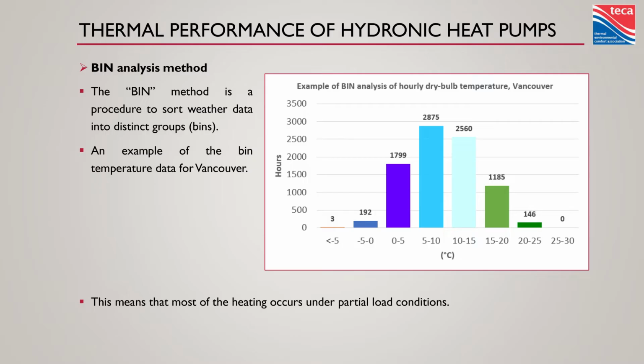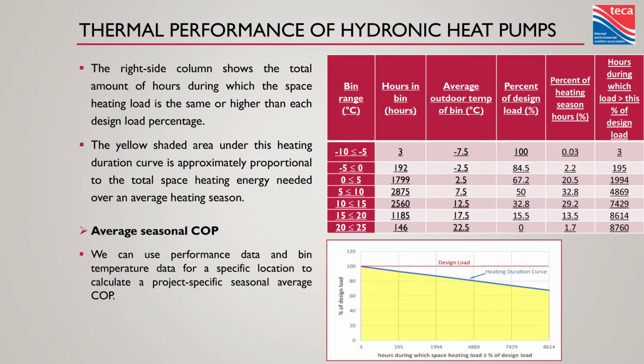But I want to point out just how little of the year we operate at design conditions. We're standing here in the greater Vancouver area. This is some bin temperature data from the city of Vancouver. Bin temperature data is basically saying how many hours in a year we spend in a certain bin or range of outdoor temperatures. So we drop these into 5-degree ranges or bins, and on average, 3 hours a year at design conditions. Meanwhile, the bulk of our run hours are right in that middle, right where we're dealing with partial load conditions where these heat pump efficiencies are much, much higher. So we need to make sure we cover the design load, but we don't necessarily have to do that with a 100% heat pump. We can do that with a heat pump that covers most of the partial load conditions and use something less efficient like electric resistance as the added capacity for those coldest days, because they're brief. At our design temperature, when we're at 100% of design, that's 0.03% of the actual heating season, so 3 hours roughly.